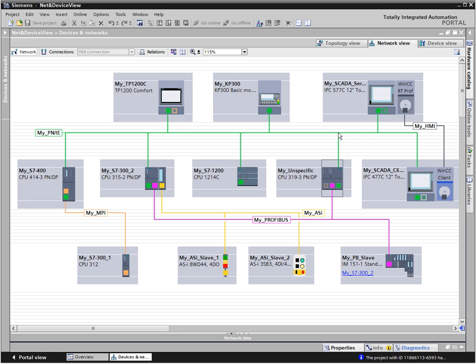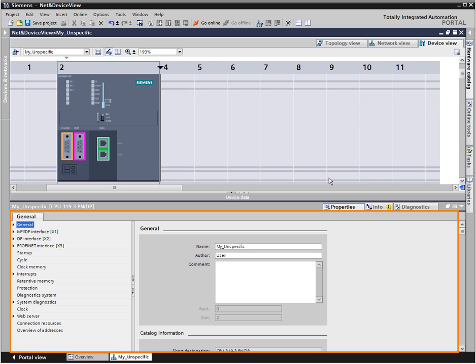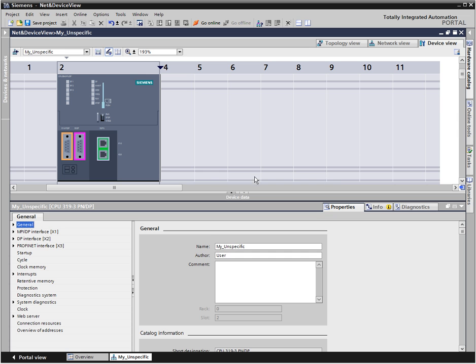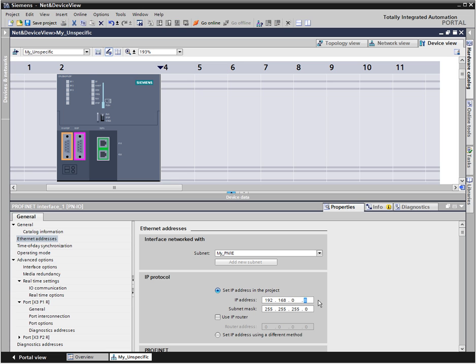By double-clicking the controller, you go to the device view. This is where you have fast access to the changeable parameters in a context-sensitive way. If, for example, the IP address of the controller is to be changed, simply click on the industrial ethernet port. The IP address parameter to be changed will be instantly displayed.